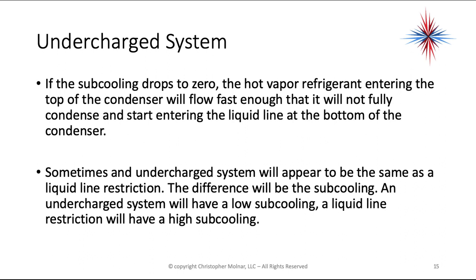If sub-cooling drops to zero, it means the hot vapor refrigerant entering the top of the condenser will flow fast enough that it will not fully condense and will start entering the liquid line at the bottom. An undercharged system will have low sub-cooling; a liquid line restriction will have high sub-cooling. That's the key difference between an undercharged system and a liquid line restriction.